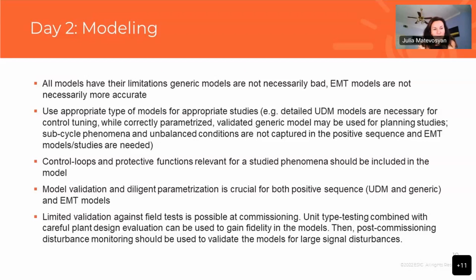And then there are phenomena that are happening on the grid where you will need to use EMT study because these types of phenomena are simply not captured in positive sequence. Control loop and protective functions relevant to studied phenomena should be included in the models, and that refers to any kind of model. Even if you have an EMT model that doesn't represent control loops and protective functions that are relevant, you will not see behavior that may actually happen on the grid.